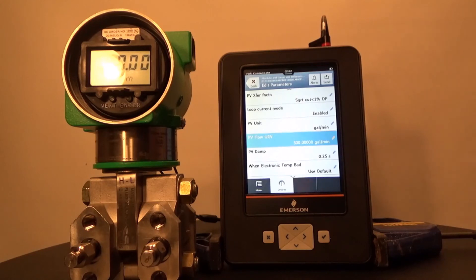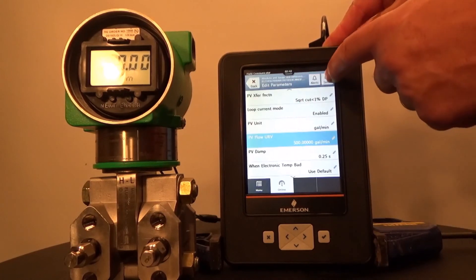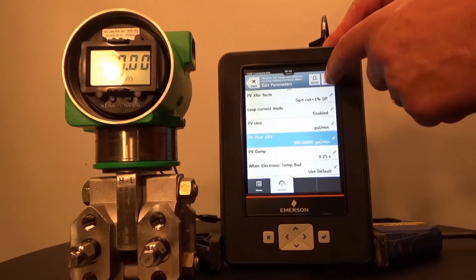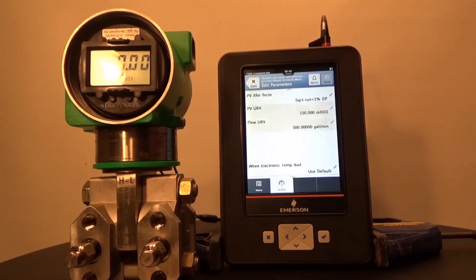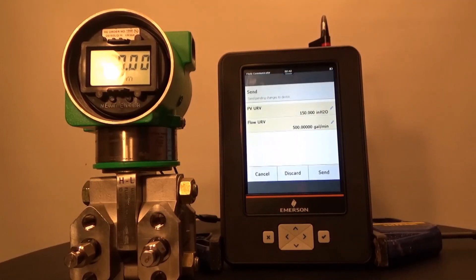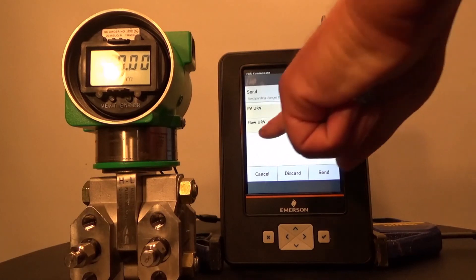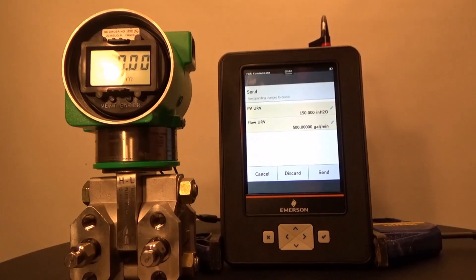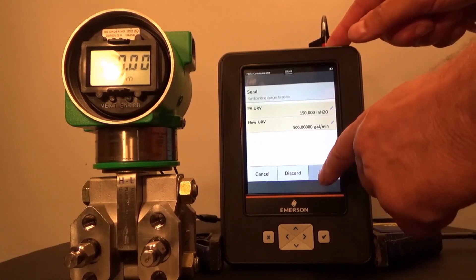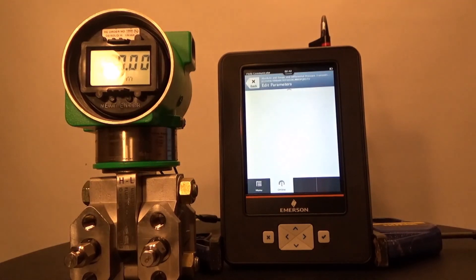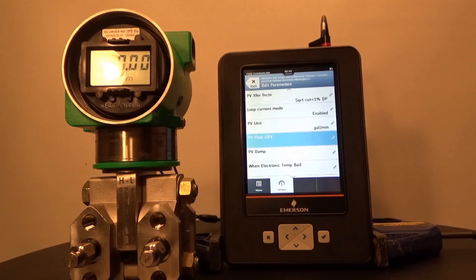You'll see a little pencil indicator here — the value hasn't been sent yet. The next step is to send it down to the transmitter, so press the Send button. The TREX will now indicate the PV URV in inches of water and the corresponding flow rate. When you see this, press Send and the TREX will return to the Edit Parameters menu.